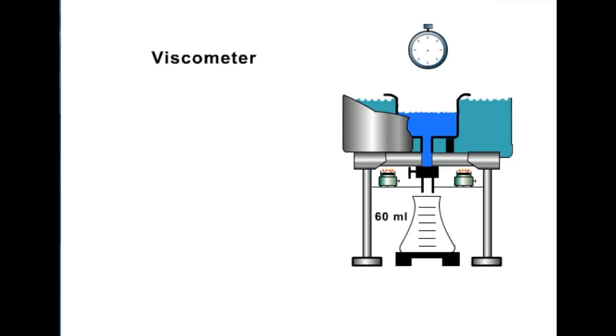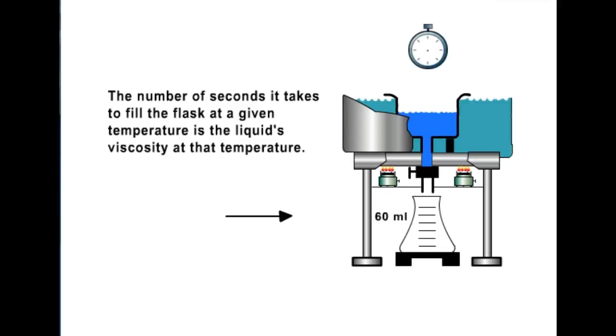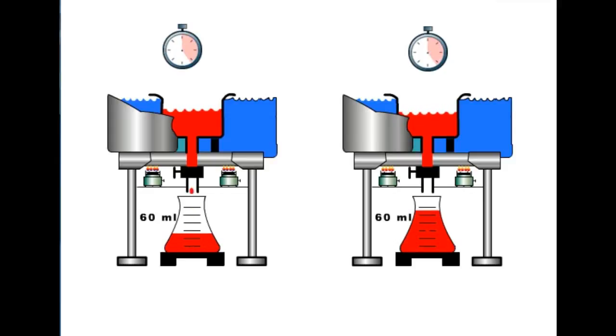A viscometer, the device used to measure a liquid's viscosity, consists of a small reservoir surrounded by a water bath, used to heat and maintain the liquid at a constant temperature. There is a small orifice below the reservoir, through which the liquid can pass once it is heated to a specified temperature. A stopwatch is used to determine how much time it takes to fill a 60 milliliter flask. The number of seconds that it takes to fill the flask at a given temperature is the liquid's viscosity at that temperature. As illustrated, the fluid on the right has a lower viscosity than the fluid on the left.